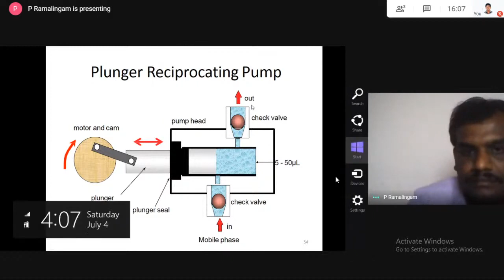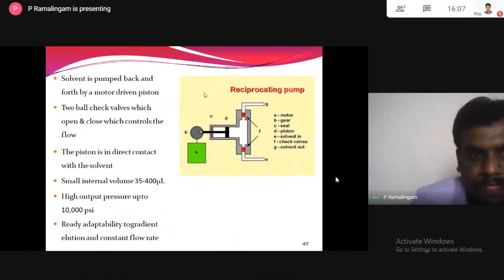The solvent pump is piston based, and it has a small internal volume, 35 to 400 microliters. The disadvantage is that it gives the mobile phase with pulses, but it has a high output pressure up to 10,000 psi. It is more suitable for adaptation to gradient elutions, large solvent capacities, and constant flow rates, largely independent of column back pressure and solvent viscosity. So to conclude, these piston-based or reciprocating pumps are more commonly used. The advantage is that they can give pressure up to 10,000 psi with a small internal volume, and the only disadvantage is the pulsed flow, which can be managed by using a dual piston pump or dampers.